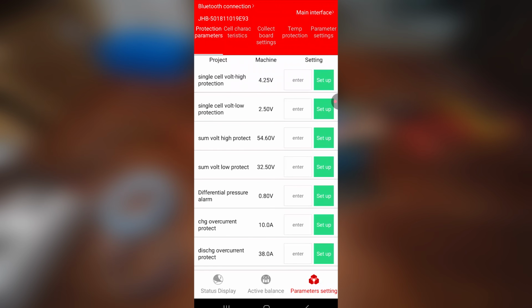We got a different pressure alarm, I would assume that's a difference in voltage, not too sure what they mean by different in pressure. And then we got charge overcurrent protection, which is actually really nice here. So I put that at 10 amps to be about 2.5 per battery, which is about 25% of their output roughly, so they can put out about 10 amps per battery.